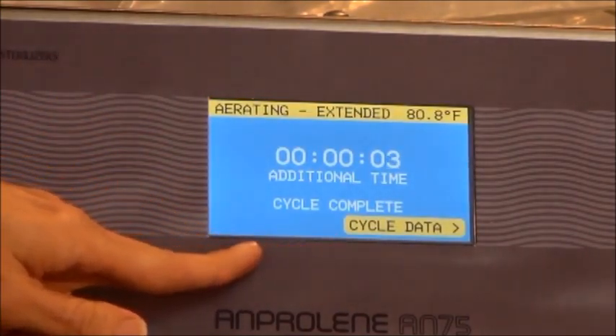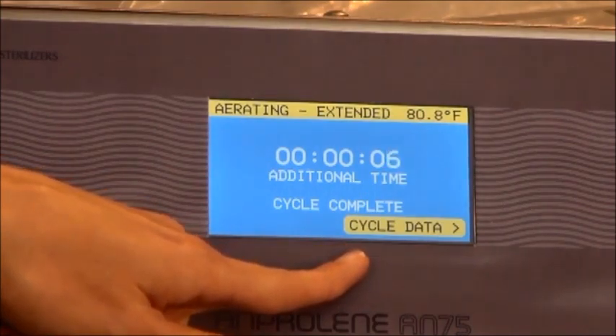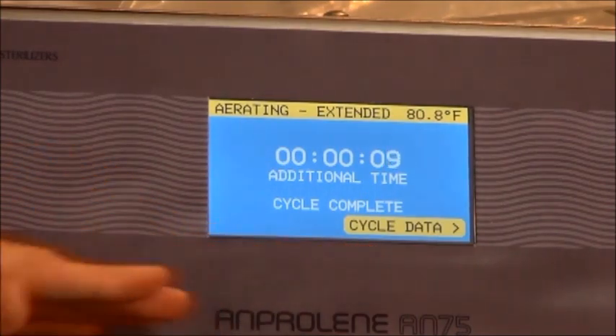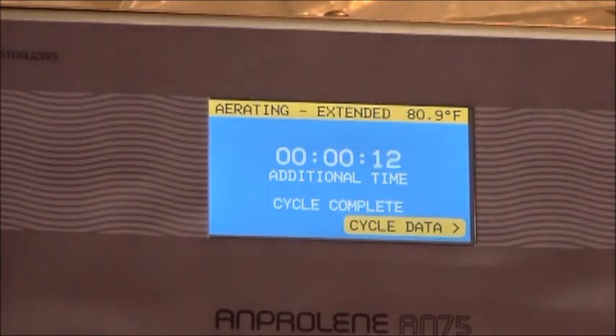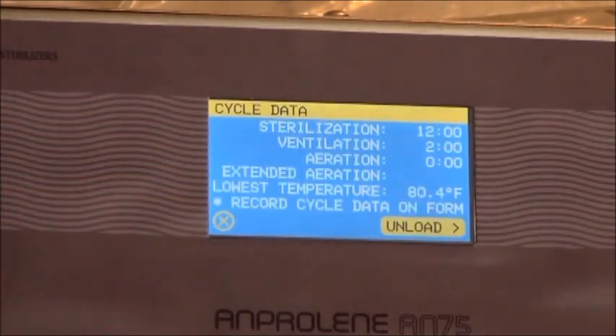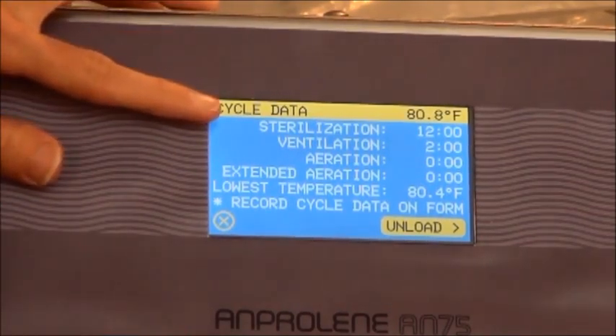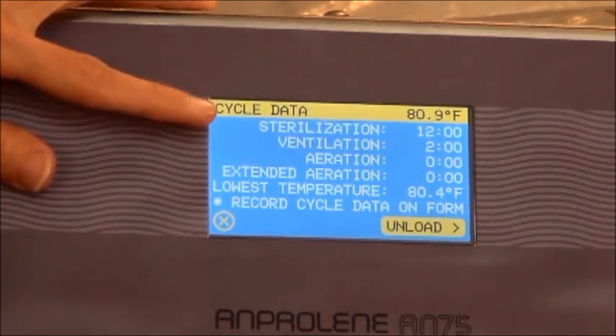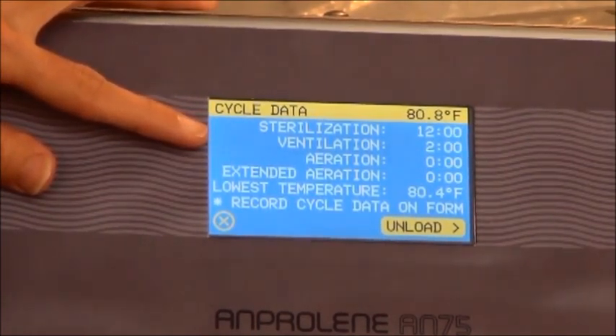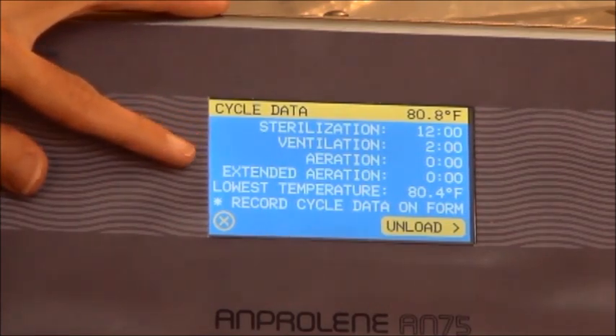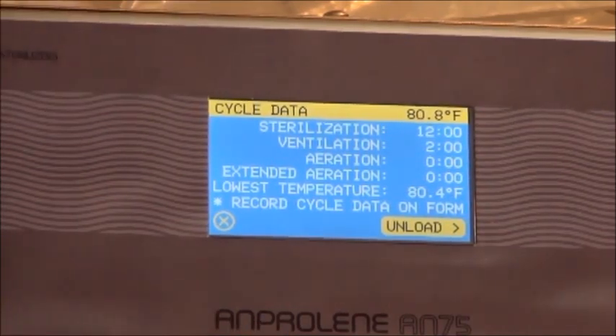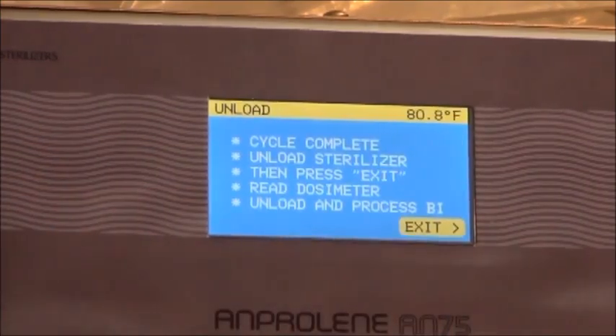Your cycle is complete, as we have not selected any additional aeration time. You can leave the items in the sterilizer until you're ready to unload. Selecting the cycle data button, you can record the length of your sterilization cycle, ventilation period, any additional aeration chosen, extended aeration, as well as temperature. By pressing the lower button, the system will walk you through all of the steps you need to follow to unload the system.